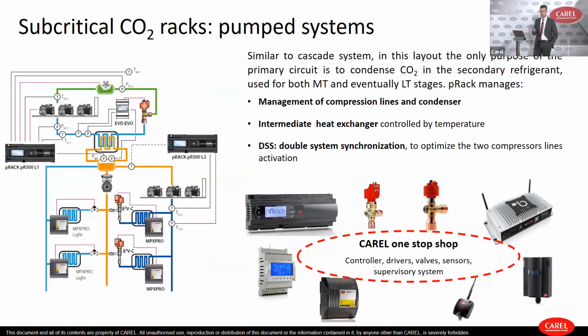Very similar to the cascade system are the pumped systems. The main difference of this system is that usually the primary circuit is just used to condense the CO2 in the big liquid receiver that is used to pump the refrigerant in liquid phase to the medium temperature cabinets, and with expansion in the low temperature cabinets or cold rooms. Of course, pRack is able to manage all the compressor lines, the condensing lines, but also the intermediate heat exchanger.